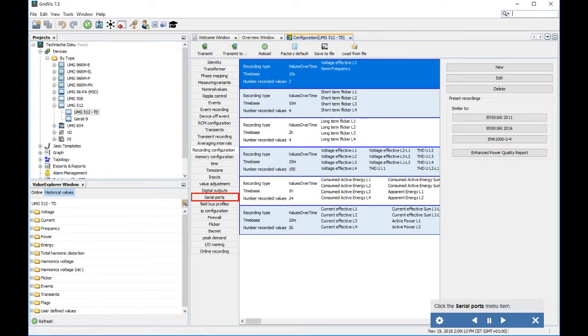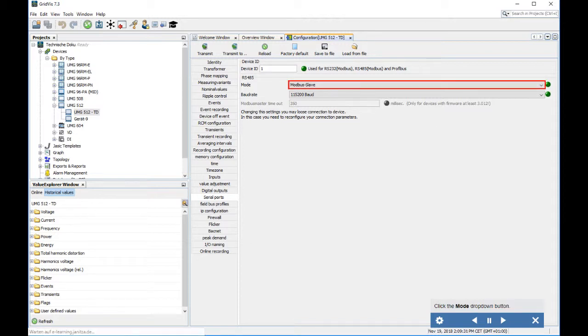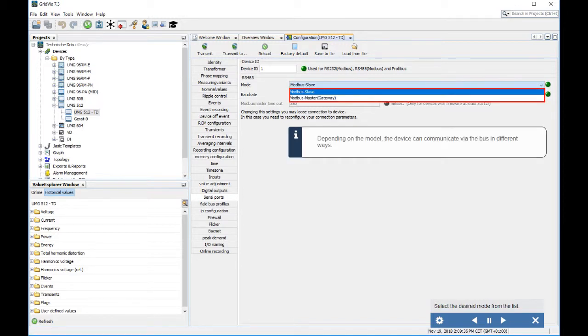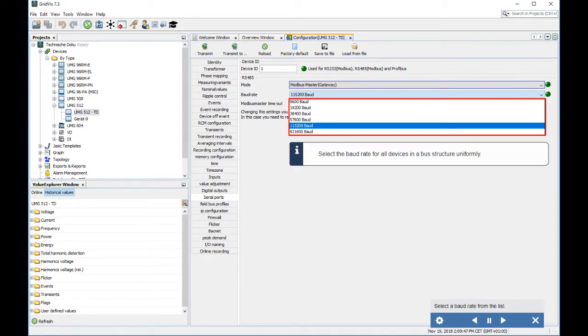Click the Serial Ports menu item. The device ID must be unique within a bus segment; for devices communicating as Modbus masters, the ID 250 is often assigned in practice. Click the device ID input field to configure the Modbus address. Click the Mode drop-down button — depending on the model, the device can communicate via the bus in different ways. Select the desired mode from the list. Click the Baud Rate drop-down button and select the baud rate uniformly for all devices in a bus structure.